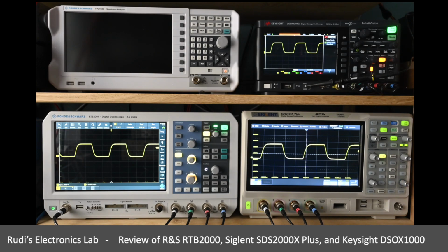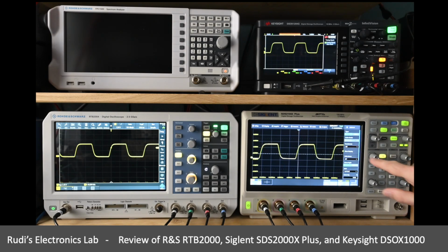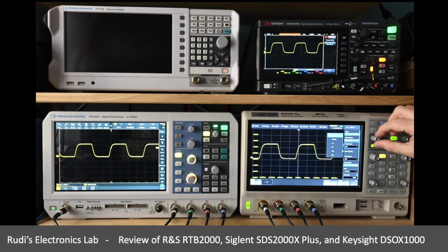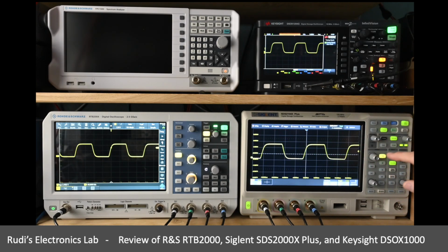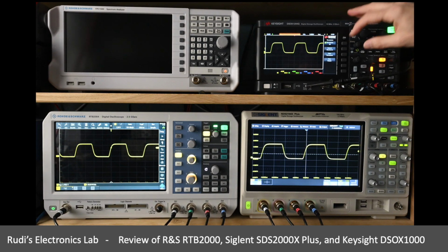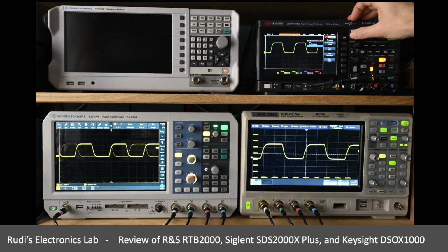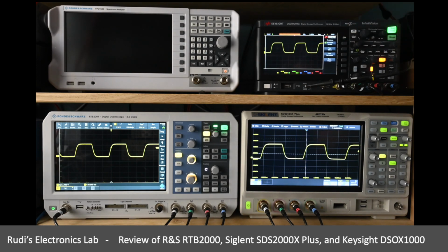Now to the SDS, let's also choose the best settings. We'll go to display, we've got a persistence mode. Here we don't have that many choices. We cannot do half a second. I'll choose a full second, which might have two glitches coming right after each other show only as one single glitch. But later we see this is not really going to be an issue here. And on the DSOX device, I will go to display, persistence, I'll go to variable persistence and also choose half a second here. So we're good. So now let's go and look at what we see here.